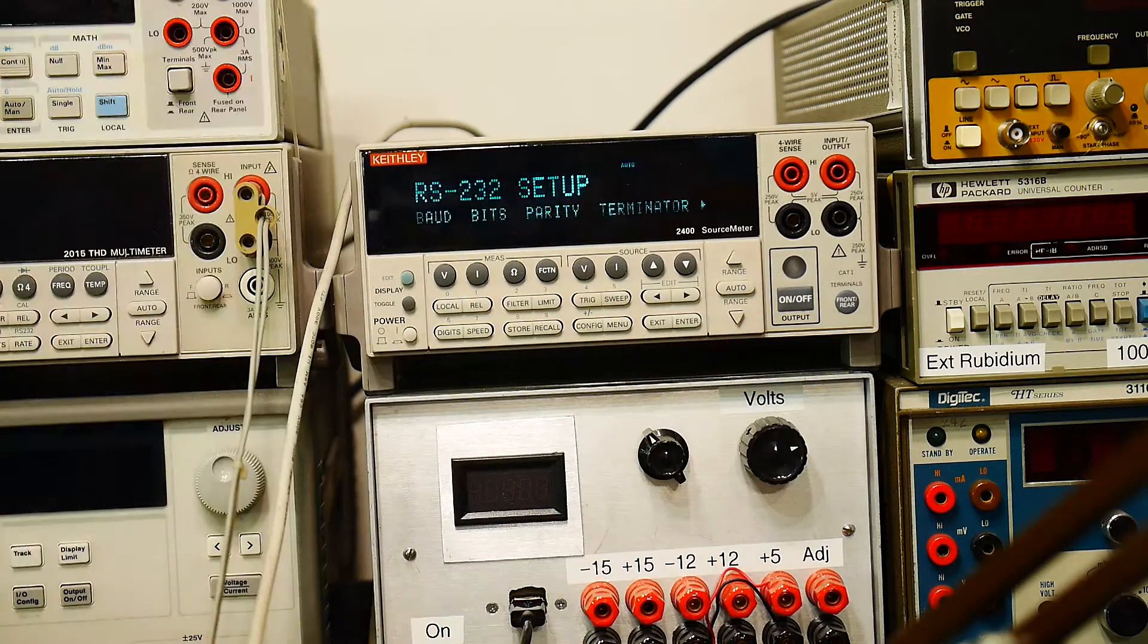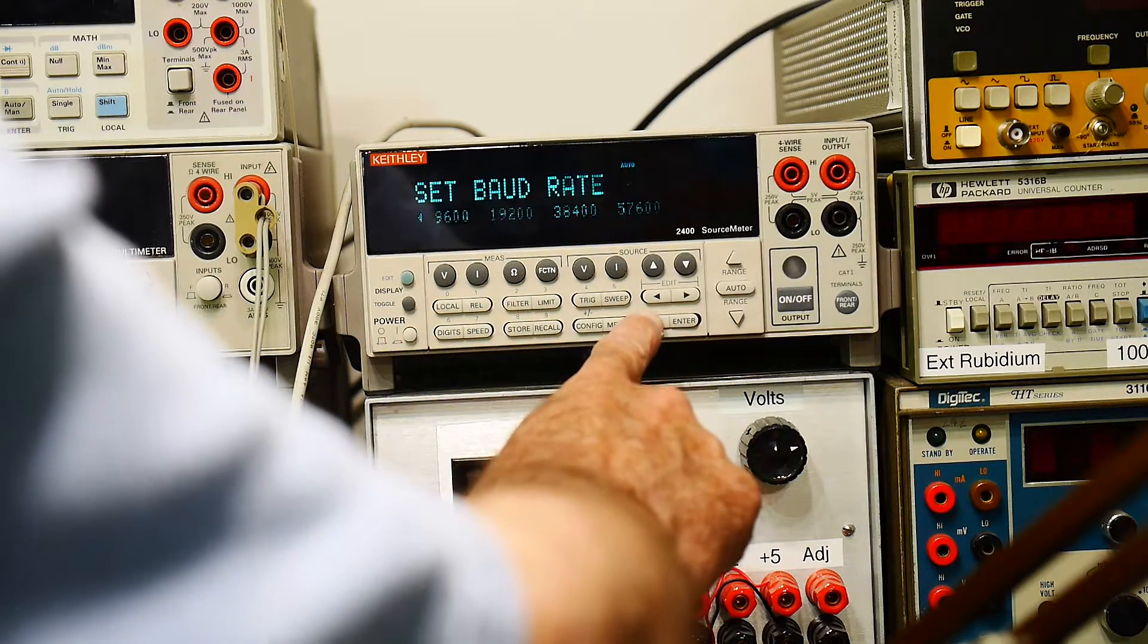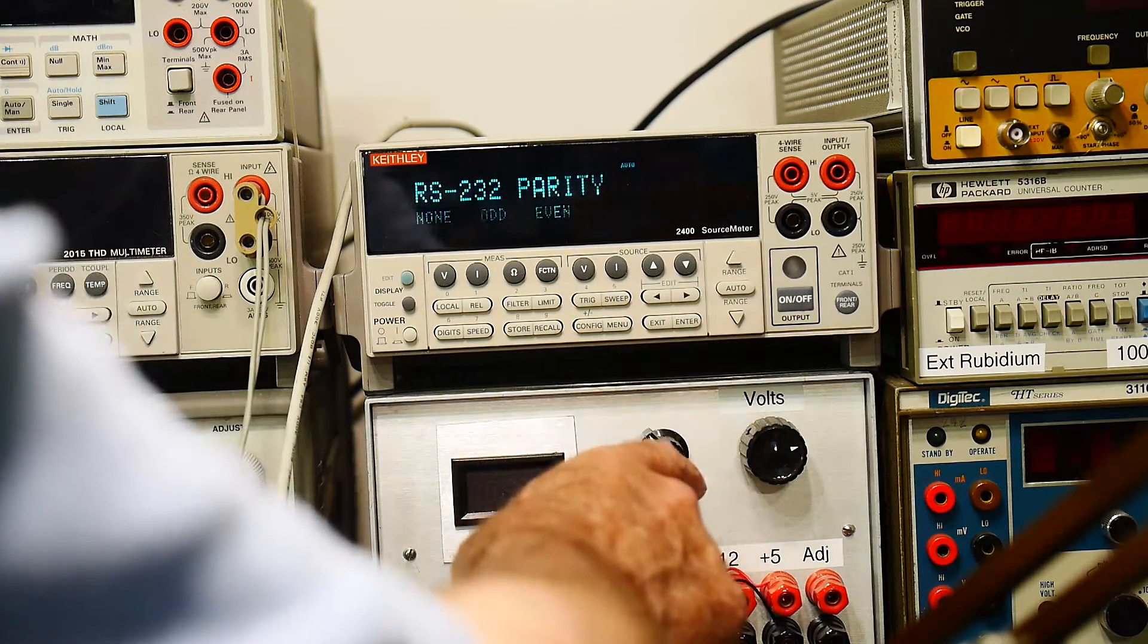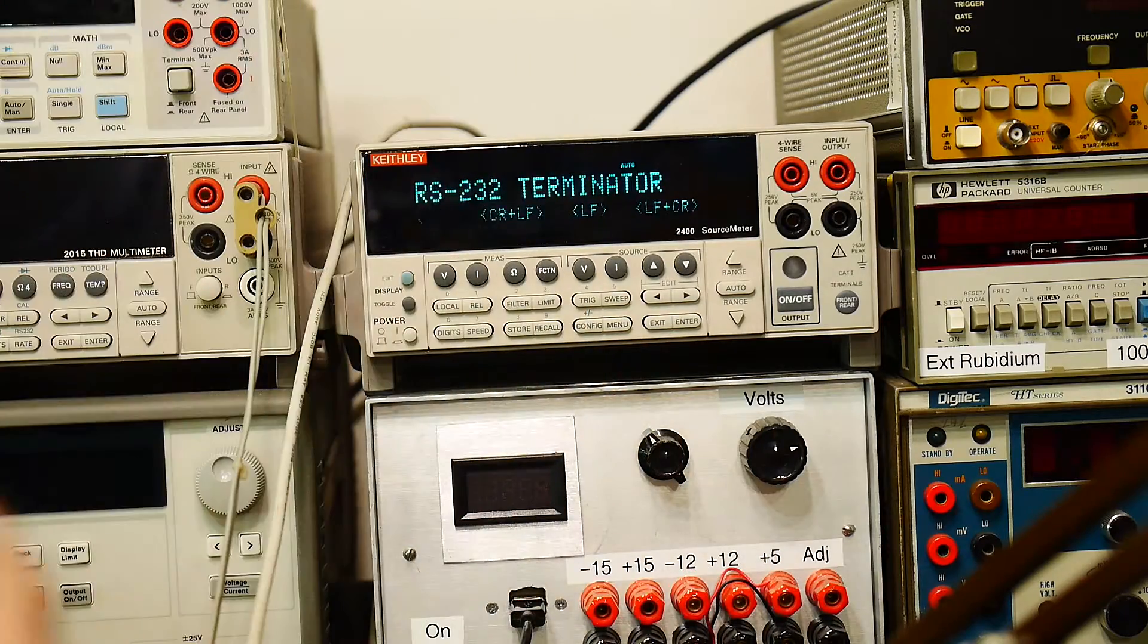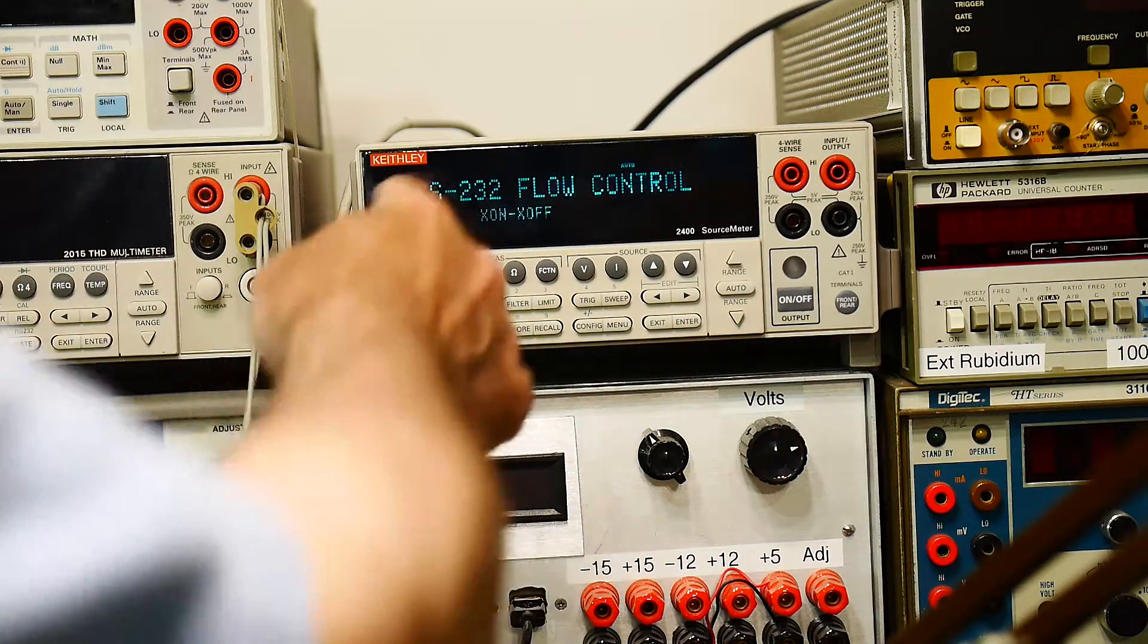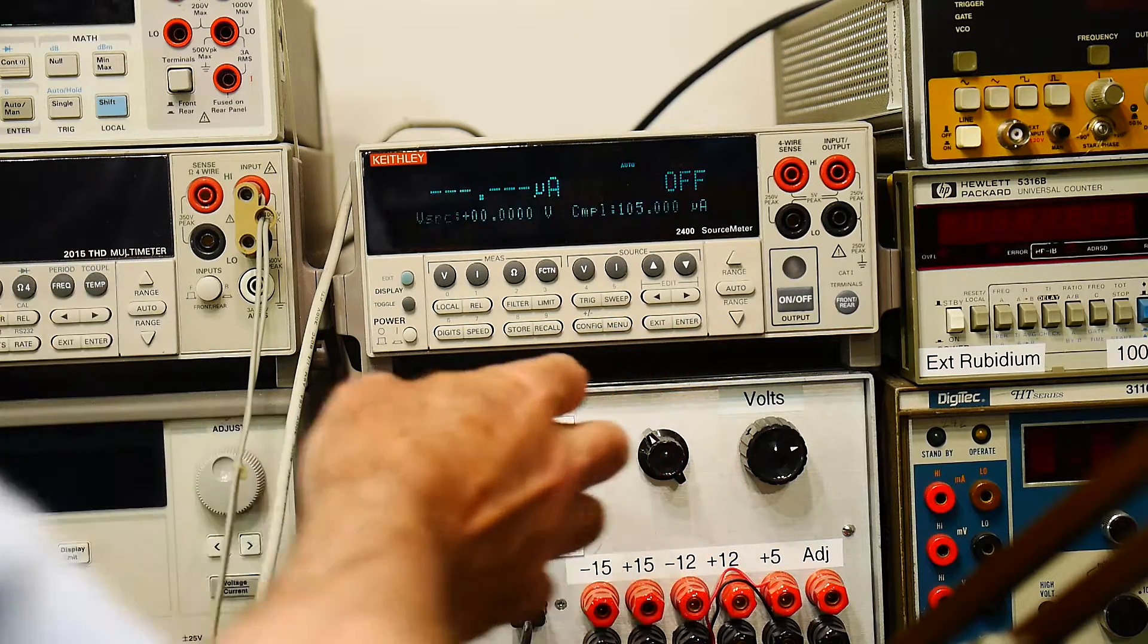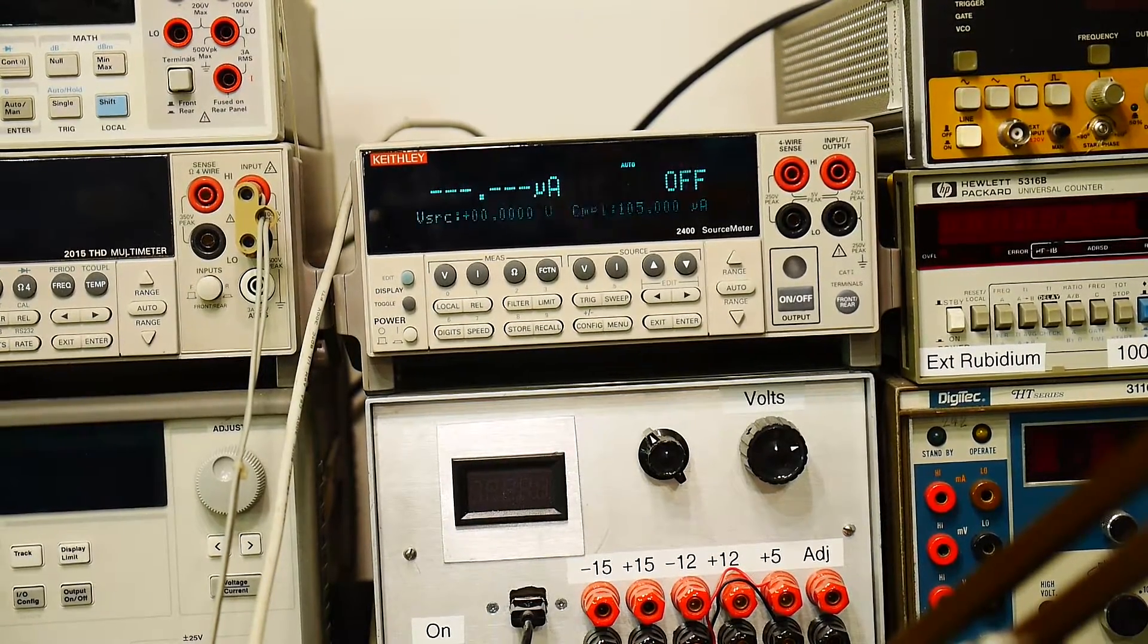We'll go back to the communications setup. RS-232. Baud rate, bits, parity, and terminator. So let's see how this thing's set up. It's set up to 19200. Eight data bits. No parity. And terminator is carriage return. So there we go. That's really all we need. Flow control. Flow control is none. Set it to X on, X off, or none. So 19200. So let's go over to a computer, hook up the COM port, and see if we can't program this thing.